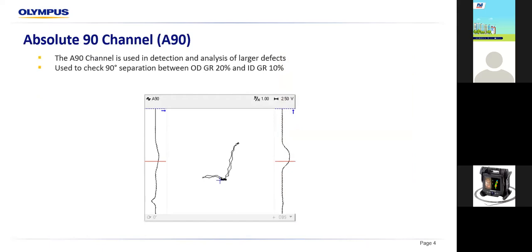So we'll go on with the frequencies or channels that are used in the ECT technique. First, you will have the absolute 90 channel, or A90. This channel is used in detection and analysis of larger defects. It is used to check the 90-degree separation between an outside diameter groove of 20% and an ID groove of 10%. So this would be a good representation of an absolute 90 channel.